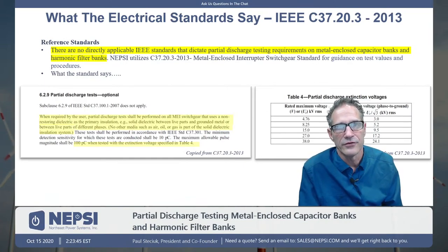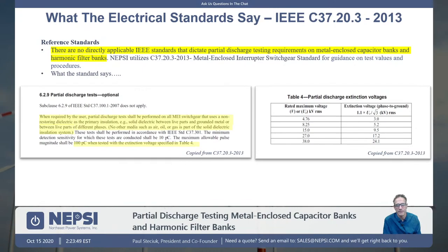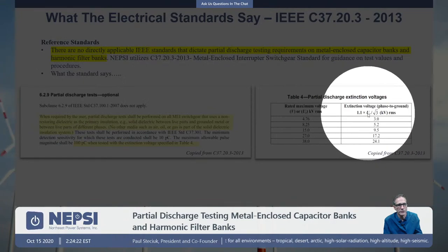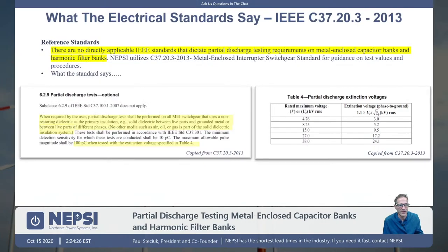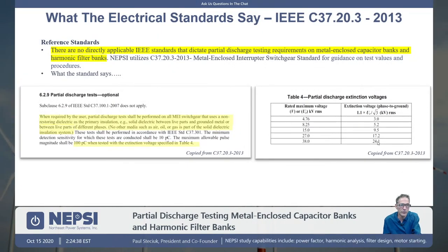So I'll just do a couple of standards. IEEE C37.20.3, 2013. Remember, for metal-enclosed capacitor banks and filter banks, there's really no standard that dictates these designs. NEPSI uses this standard, C37.20.3, a switchgear standard, a load interrupter switchgear standard, to come up with our test values. Basically, we're increasing our voltage to the corona level, and then we're dropping it back down to the extinction level, which is defined by 1.1 times the rated voltage of the equipment divided by square root of 3. So obviously here we're talking about line-to-neutral voltage with a 10% overvoltage. So once we come back down, we have to make sure, if it was 38 kV gear, that at 24.1 kV we would be below 100 picocoulombs, and that's really what the test is involved with.